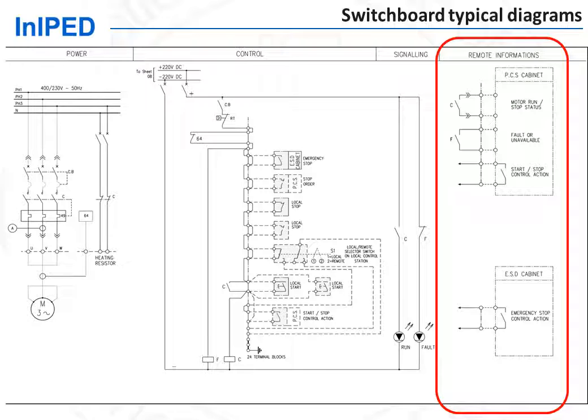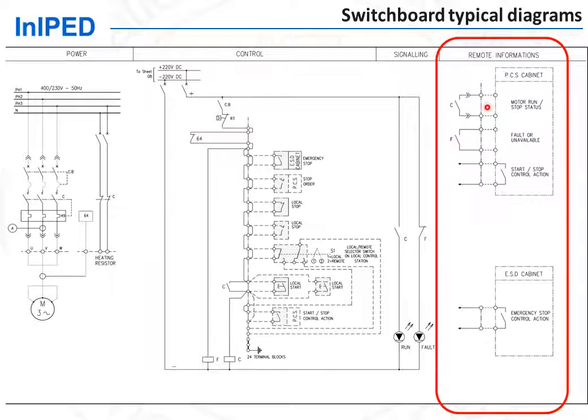Controls must also be defined — for instance, for a motor, control signals from the process control system to start or stop the motor, as well as signals from the process safety system to shut down the motor in an emergency. These signals exchanged between the process control system and emergency shutdown system with the MCC are shown on switchboard typical diagrams.